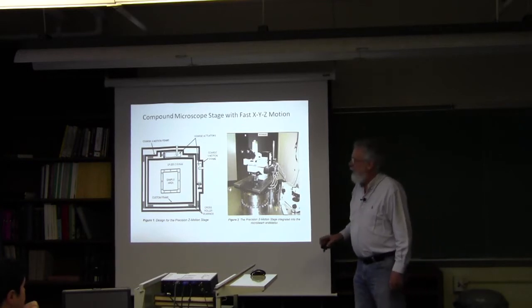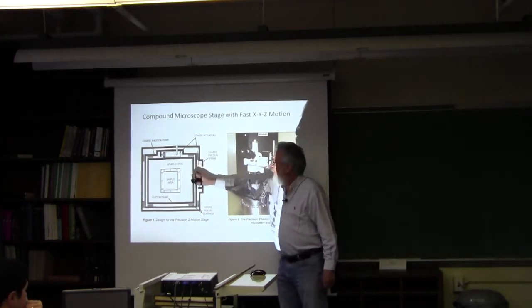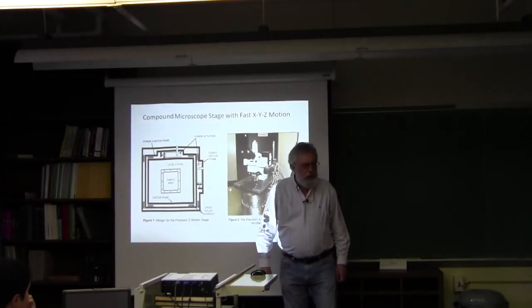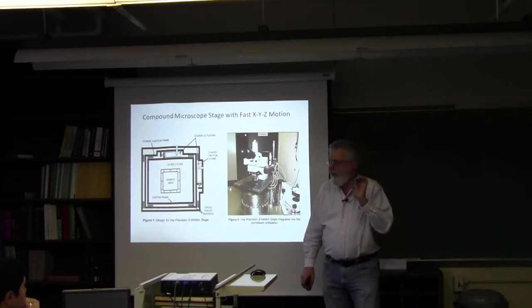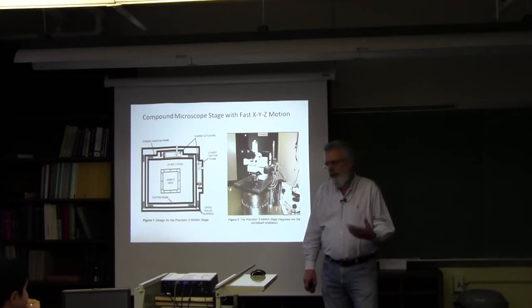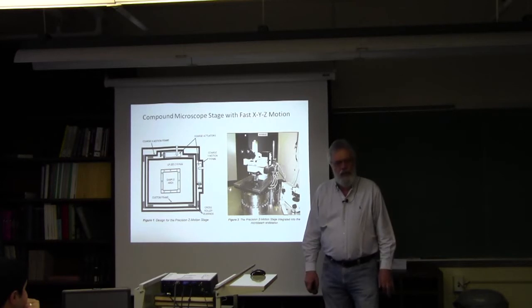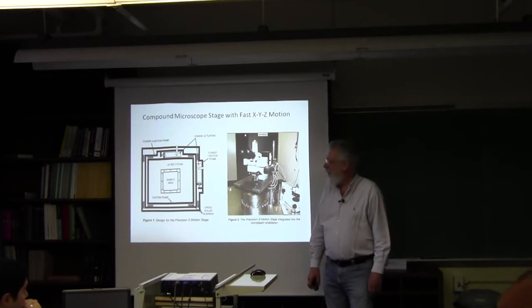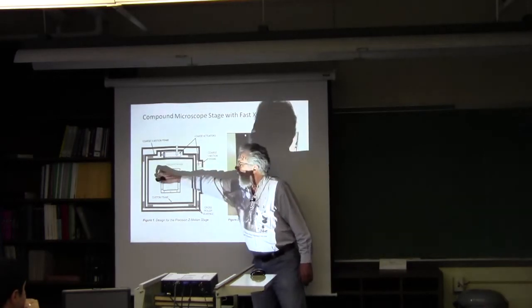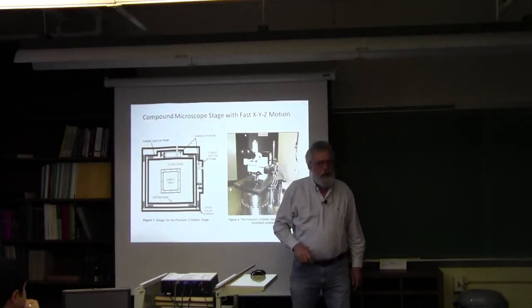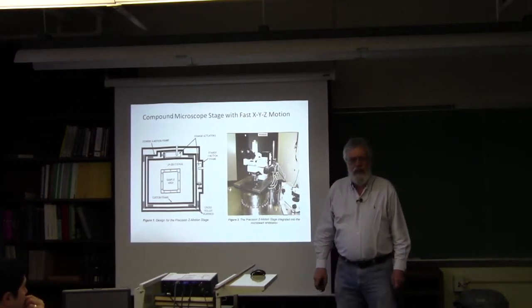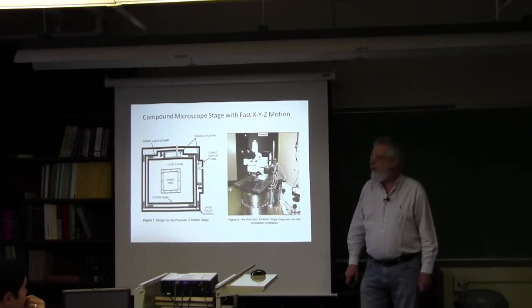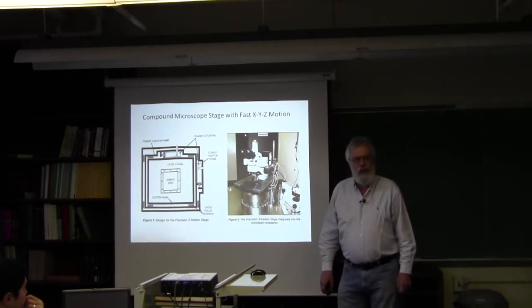The microscope stage actually has two parts. There's an outside frame which is moved by stepping motors. It can move plus or minus five millimeters, which covers the size of our sample dish. It goes about two millimeters a second but has only about six micron resolution, which isn't adequate for aiming at things with micron precision. So inside that there's another stage which is a piezoelectric drive stage which has plus or minus a hundred micron movement in the X, Y, and Z directions.